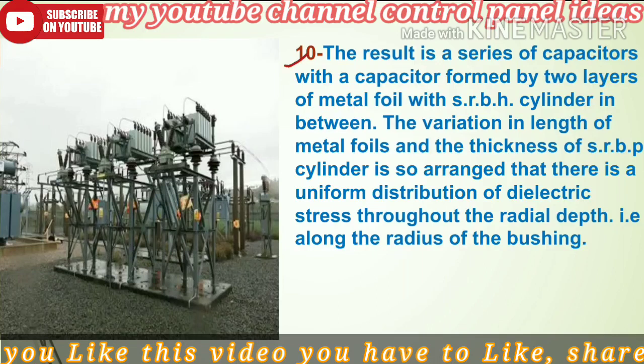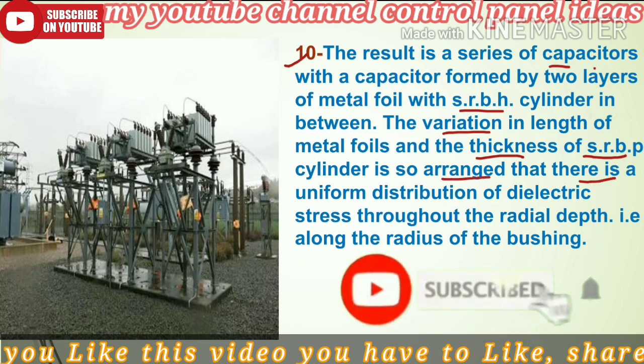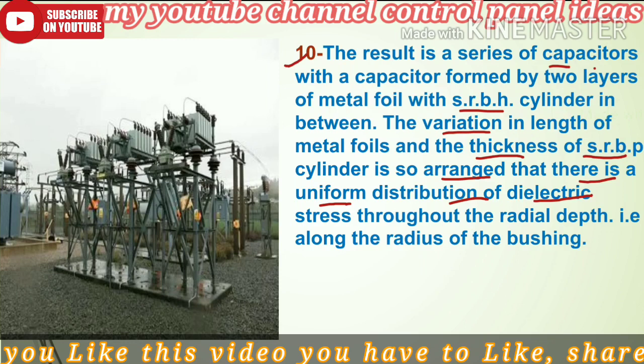Point 10. The result is a series of capacitors, with a capacitor formed by two layers of metal foil with an SRBP cylinder in between. The variation in length of metal foil and the thickness of the SRBP cylinders is so arranged that there is a uniform distribution of dielectric stress throughout the radial depth, that is, along the radius of the bushing.